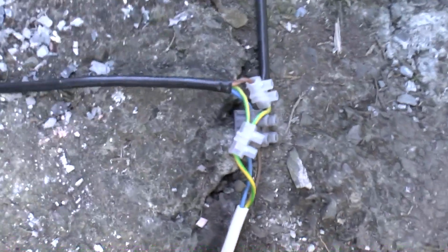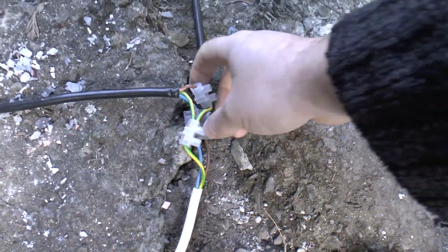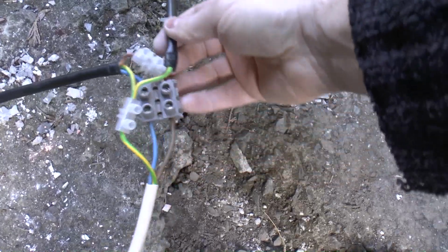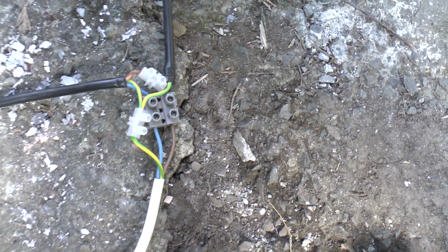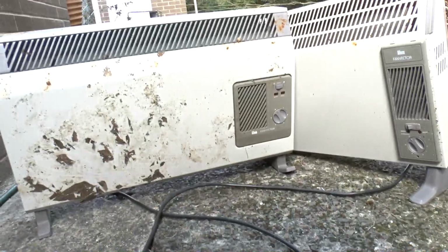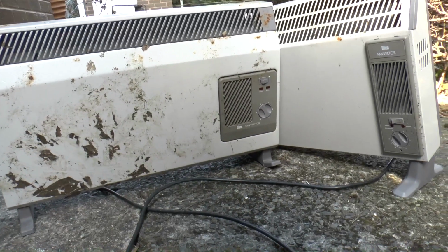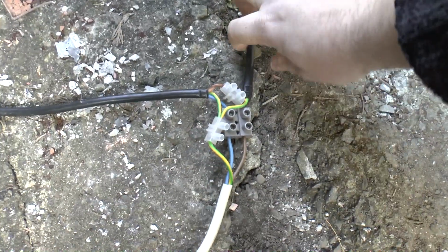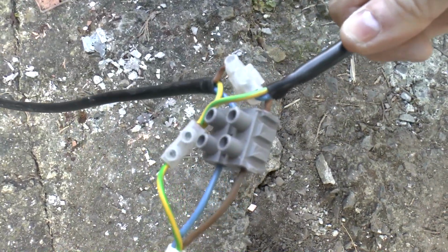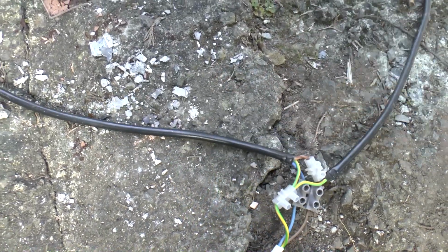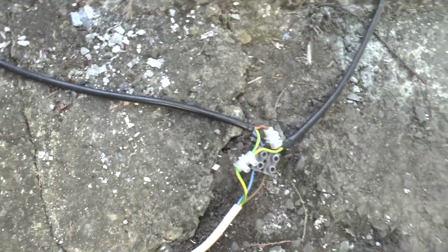Also, we have this white cable which has a similar arrangement, where the live comes in, goes out to one of these 2.5 kilowatt Glen fan heaters. Then the neutral comes in from that heater, goes to the live of the next heater, and the neutral from that goes back and flows down. Earths are in parallel. You can see there are no other cables.